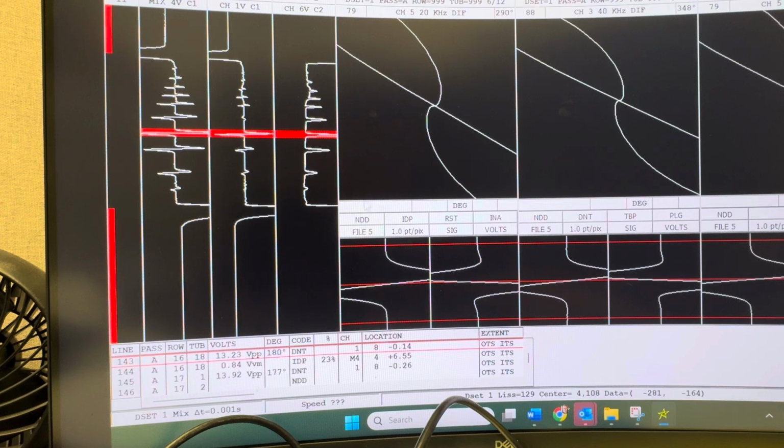So how do you do it? Well, I'm only using a standard bobbin coil probe here with differential and absolute arrangement, so they're aligned already. They're only separated by about 30 thousandths. One of the pair of coils is used for the channel 2, 4, 6, and 8, and then the two together are for channel 1, 3, 5, and 7.